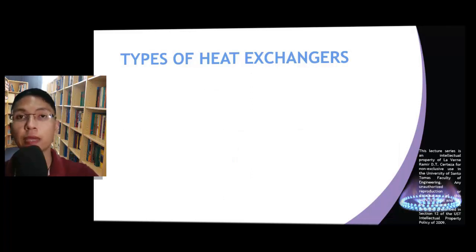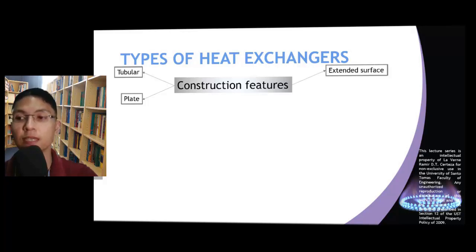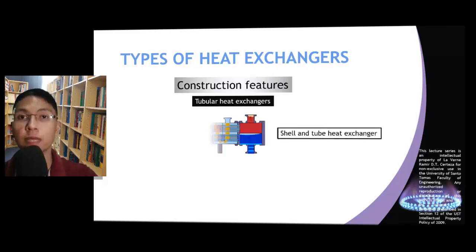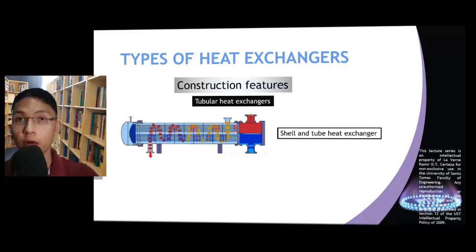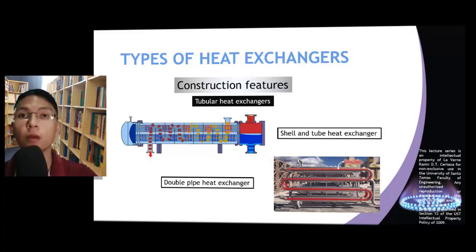The third characteristic by which we can categorize heat exchangers is related to how they are constructed. Under this criterion, we can categorize them as tubular heat exchangers, plate heat exchangers, heat exchangers with extended surfaces, and heat exchangers with regenerative matrices. Tubular heat exchangers are built by putting rows of tubes in parallel to one another, such as in a shell and tube heat exchanger, or by concentrically putting one tube inside another, such as in a double pipe heat exchanger.